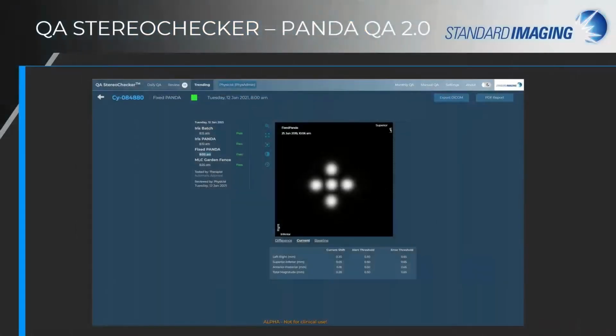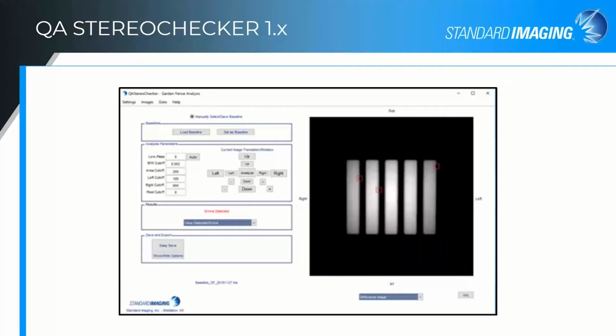From the old to the new, we have added an iris PANDA test to the existing fixed cone PANDA test. As a reminder, PANDA stands for Position and Delivery Analysis. This test replaces the Accuray film-based AQA test. Not only does it replace the AQA test, it provides more complete information as the results include the left-right, superior-inferior, and anterior-posterior shifts in addition to the total magnitude shift.